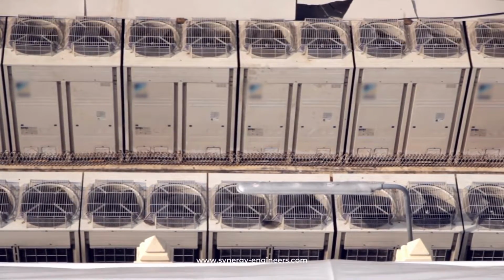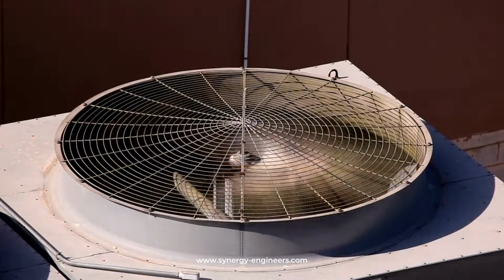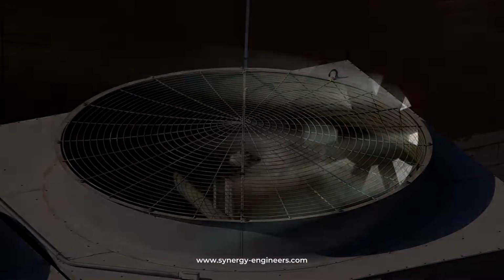And then if we have a loss of one fan, the sequence is programmed so that the other remaining fans that are in operation are going to speed up and deliver the same amount of airflow with a reduced number of fans as it was providing with the original design normal operation number of fans moving forward. So control is very similar.